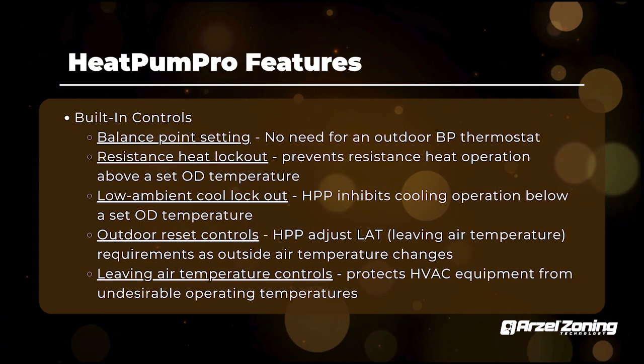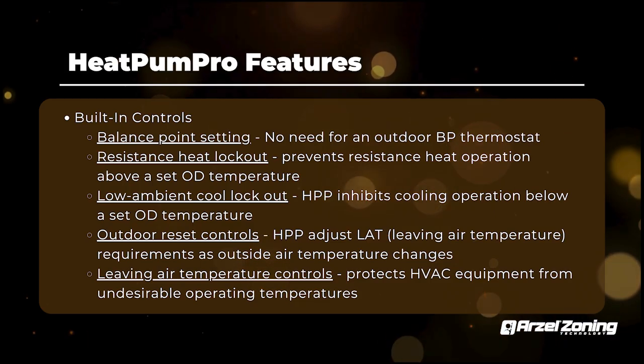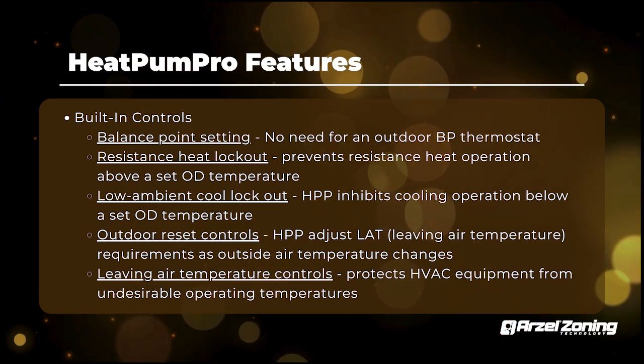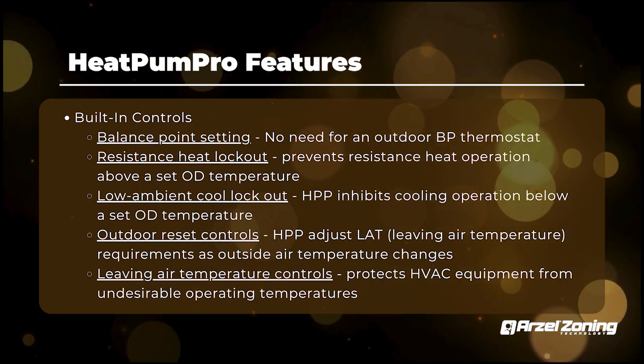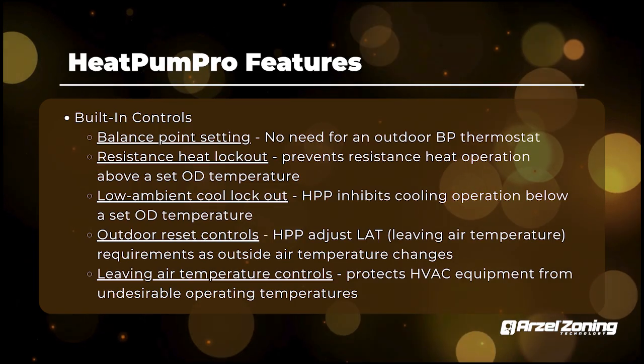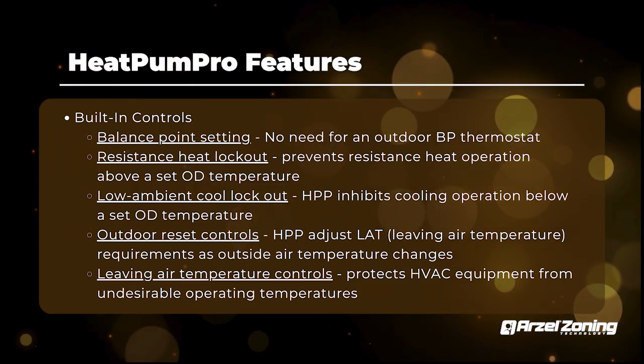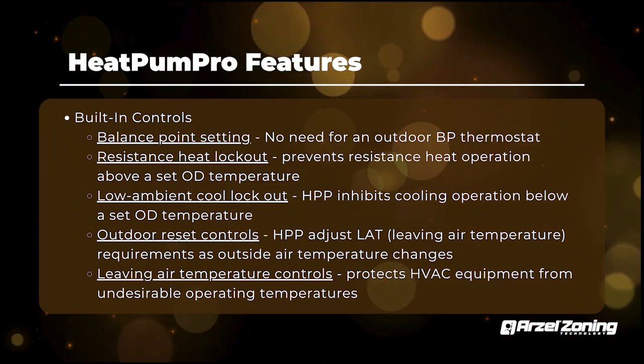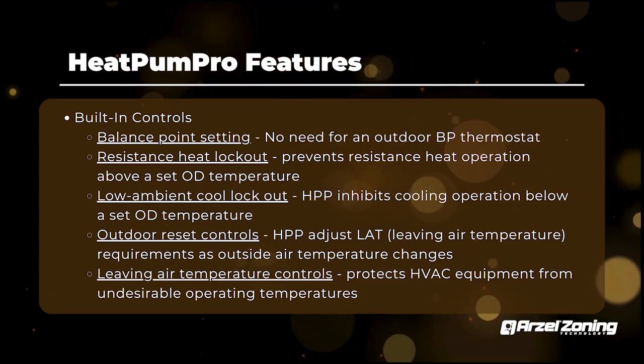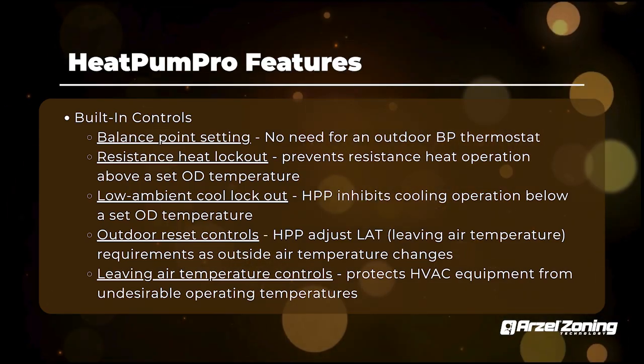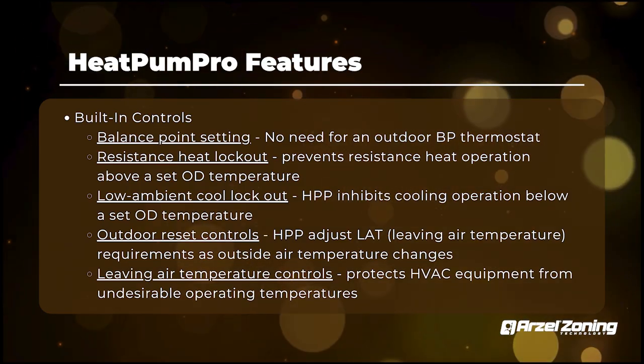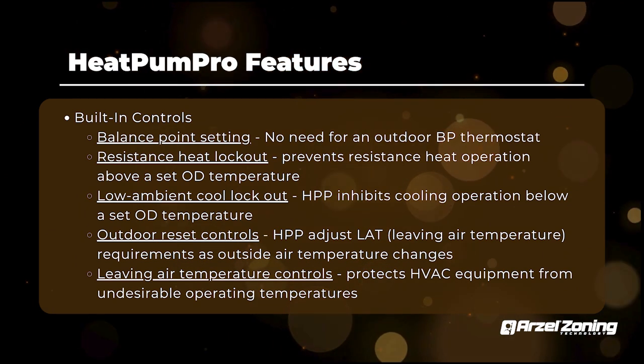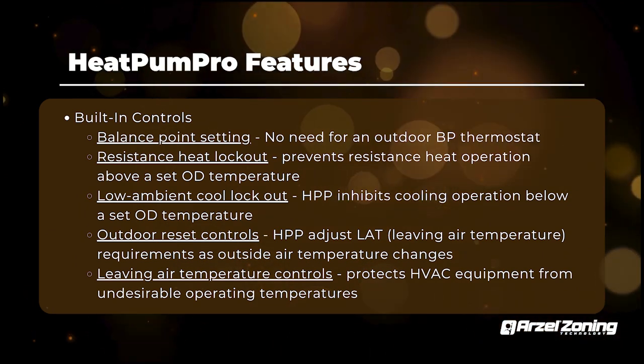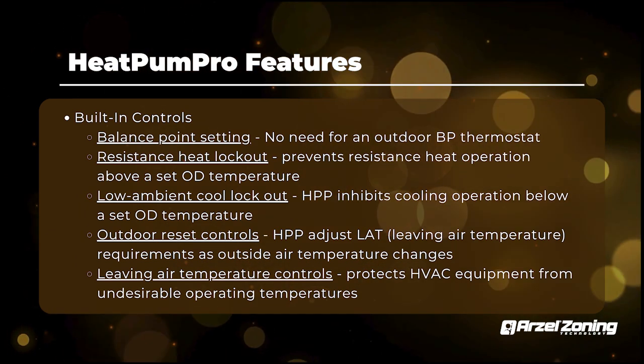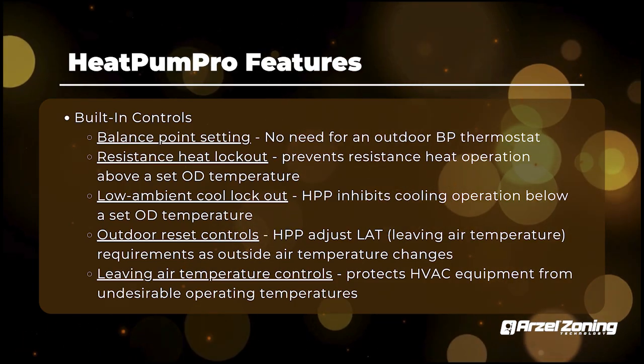So some of your built-in features that are going to come standard with every HeatPumPro is it's going to have your balance point setting. So with that outdoor air temperature sensor, it's going to have your balance point, so your changeover setting. So if you guys are doing dual fuel, you want the compressor to shut off on the heat pump at 20 degrees, 30 degrees, whatever it may be. You'll set that, and the panel automatically changes to your auxiliary heat at that temperature. So it's a nice added feature. You don't need dual fuel stats and that kind of stuff. Everything's built into the panel.